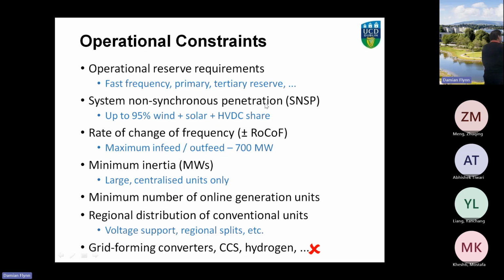At the minute, there's a requirement for at least 8 units to be online. The plan for 2030 is to reduce that to 4, maybe even 3 units, so operating a system with just 3 synchronous units on the system, and those generators should be distributed around the system.